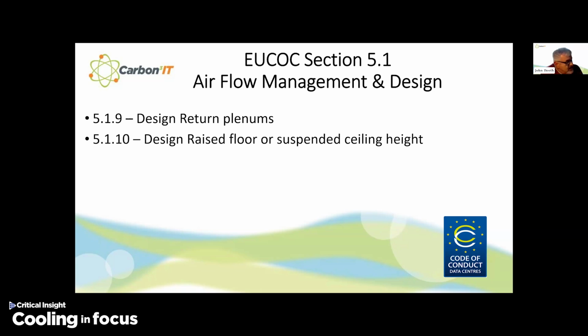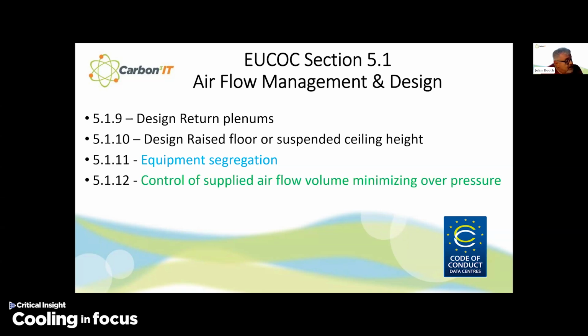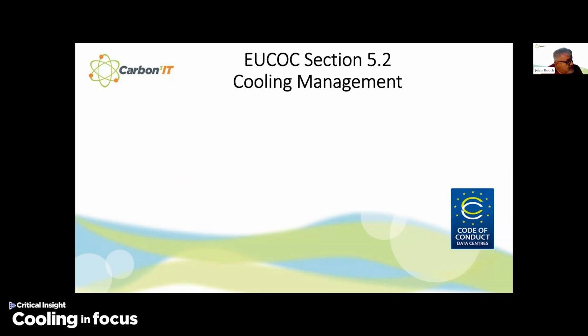Think about your design, raised floor and suspended ceiling height. Think about equipment segregation, and that's for legacy and tight environmental control equipment, where you might need it either to be cooler and have a smaller range of humidity, or a transmission piece of kit which can actually operate at higher temperatures. Your control of supplied air volume, minimizing overpressure.